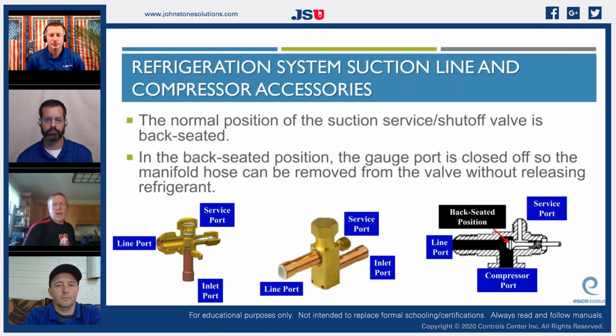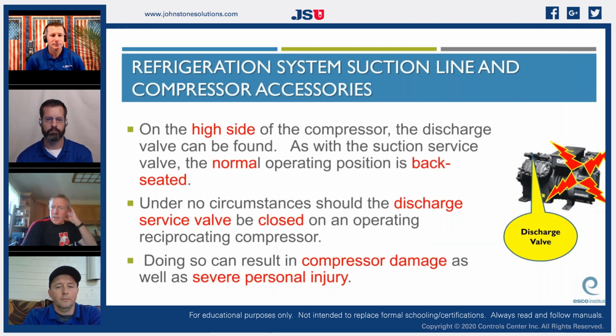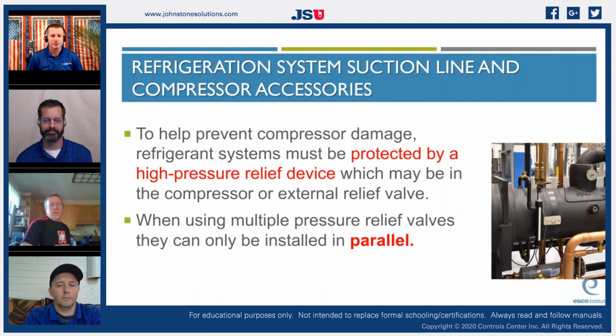I'm not going to spend time on the valves. On semi-hermetic compressors, they never want you to start them with the discharge service valve closed. You can damage the compressor, and you can actually cause personal injury too. To help prevent compressor damage, refrigerant systems must be protected by a high pressure relief device, maybe the compressor external relief valve. In residential units, it's usually an internal valve, like a check valve or something like that. It keeps them from overpressurizing.